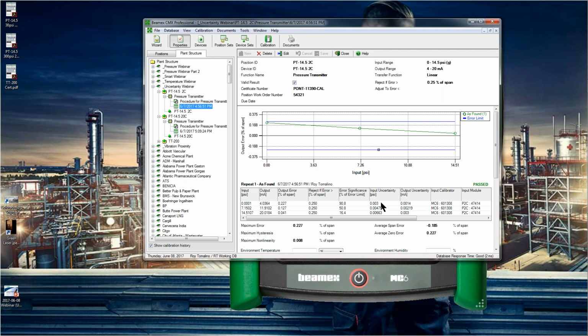So what have we learned from this? You've learned that there is a smaller uncertainty with the smaller pressure module. When we use a larger pressure module to measure the small value, there's a higher uncertainty. And we're looking at that right here from the table.